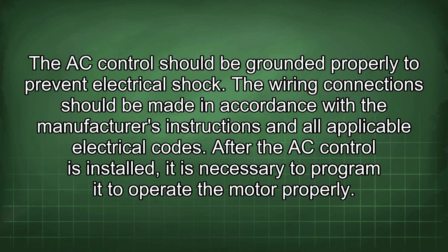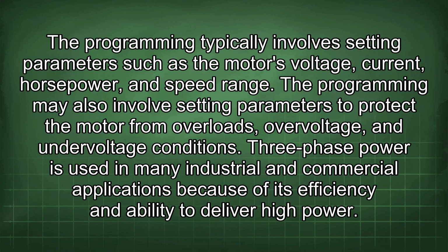After the AC control is installed, it is necessary to program it to operate the motor properly. The programming typically involves setting parameters such as the motor's voltage, current, horsepower, and speed range. The programming may also involve setting parameters to protect the motor from overloads, overvoltage, and undervoltage conditions.